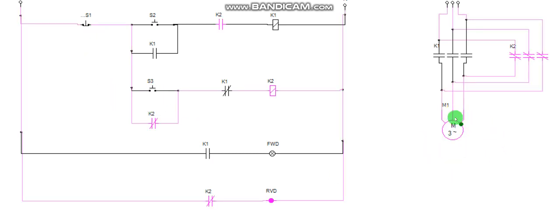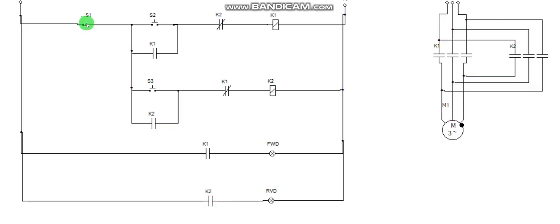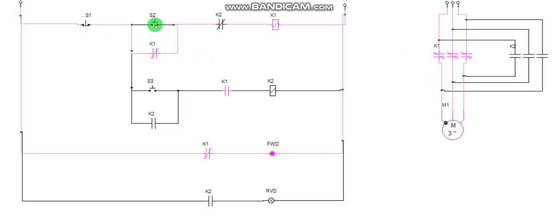Look at it going the opposite way. Then you notice that this contactor closes to give me counterclockwise operation. Then watch this one close this time to give me clockwise operation. So just take a look at this. Forget about this design. We are going to take care of this in our subsequent practice. So I just want to illustrate how you can configure an induction motor to offer two directions of rotation. All right, so let's go back to our design software.